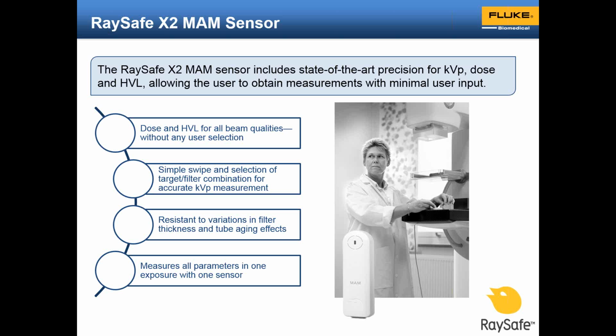The RaySafe X2 mammography sensor has all of the same great features as the RF sensor, but specifically designed for making simple mammography measurements, again with very limited user input needed. One of the challenges in making mammo measurements is the wide range of different target filter combinations used in systems today, and these systems are constantly evolving. Our relationships with the mammography manufacturers means we are involved during the development of new systems, and our calibrations are developed with direct input from the manufacturer.